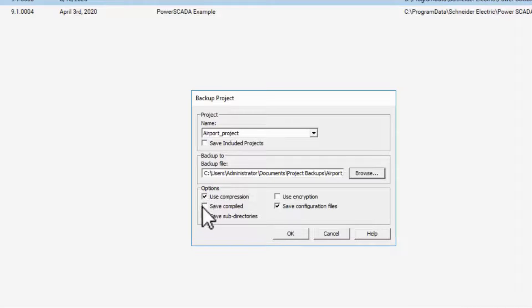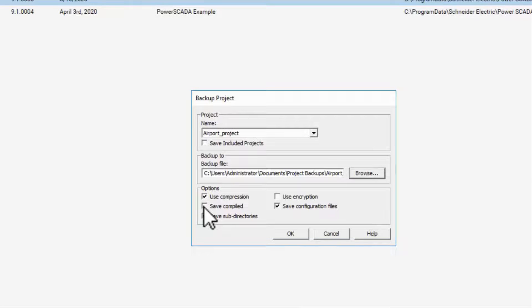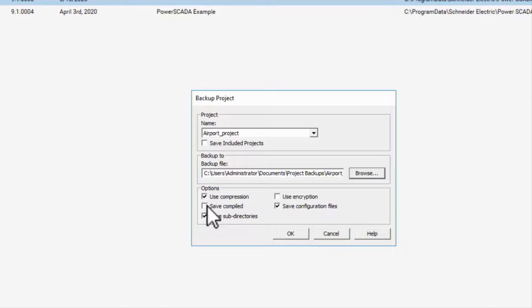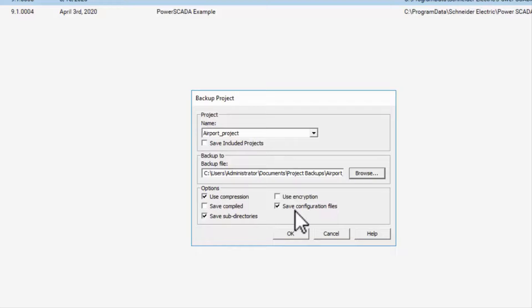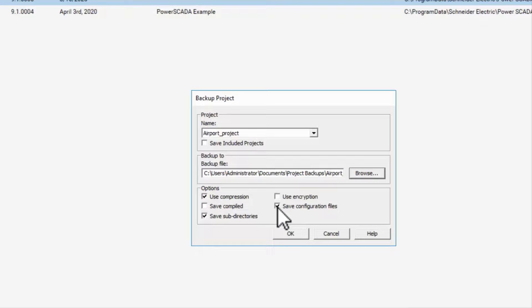Saving the compiled project is only necessary for special runtime-only clients and otherwise should be left unchecked to save space. If you backup configuration files on a development machine, you will override whatever is already there, which may be a backup from the server. Always save sub-directories because the folder called Profile Instance Configuration is necessary for I/O Device Manager.